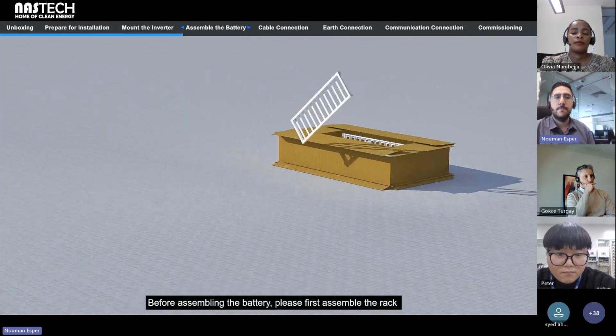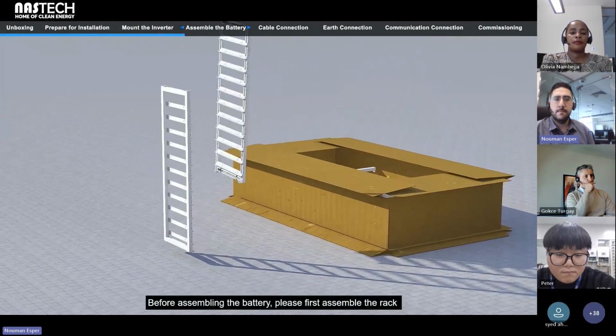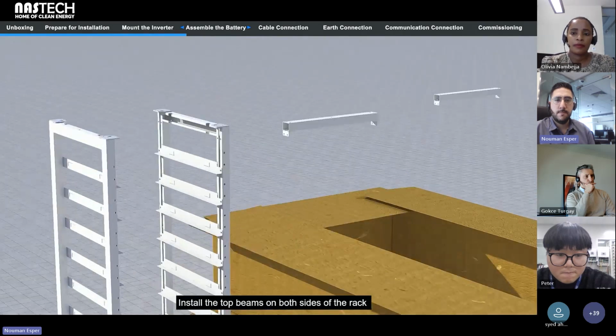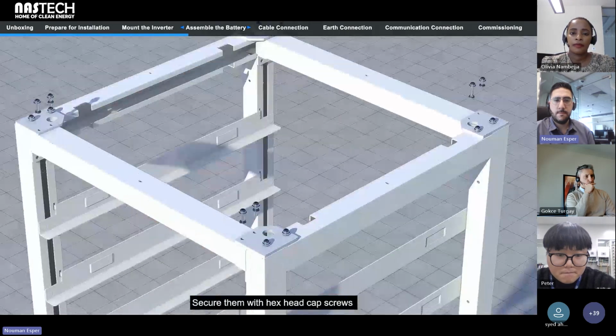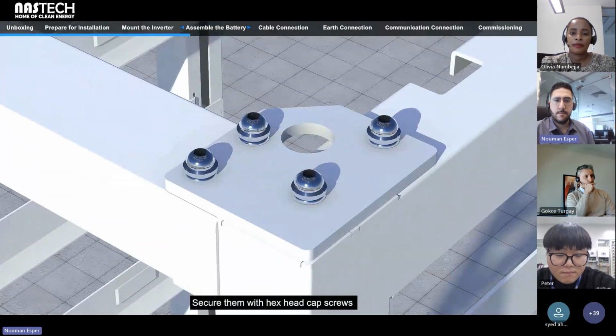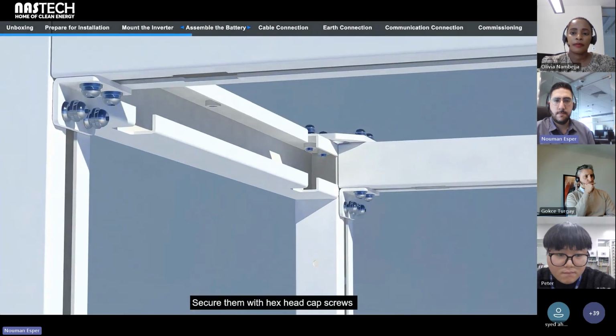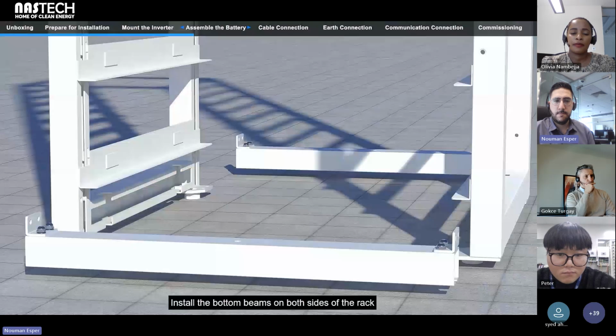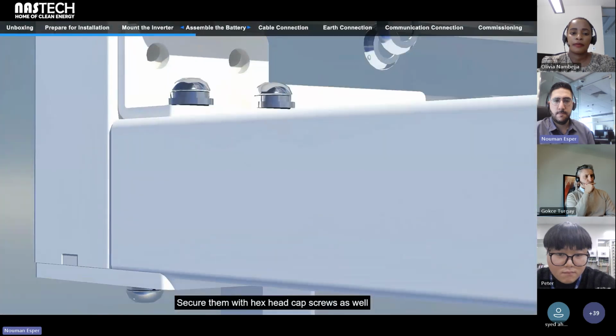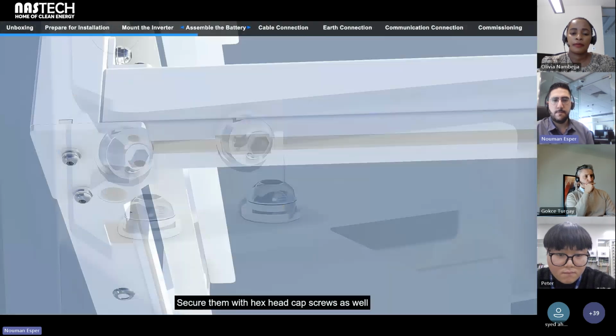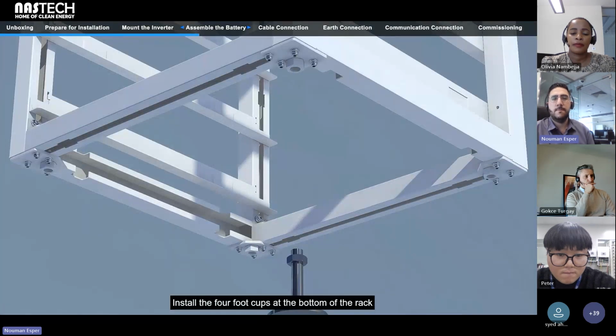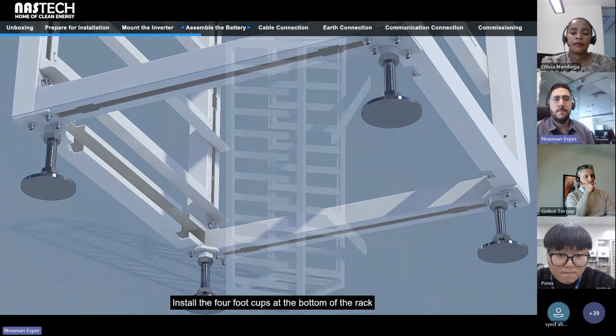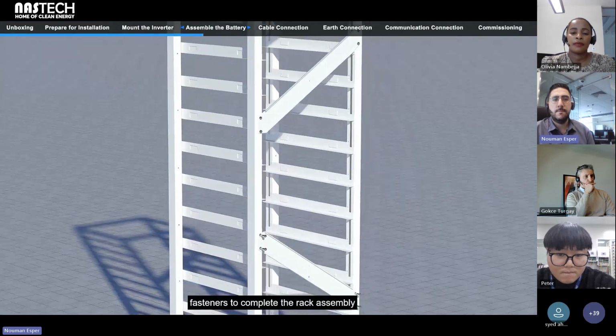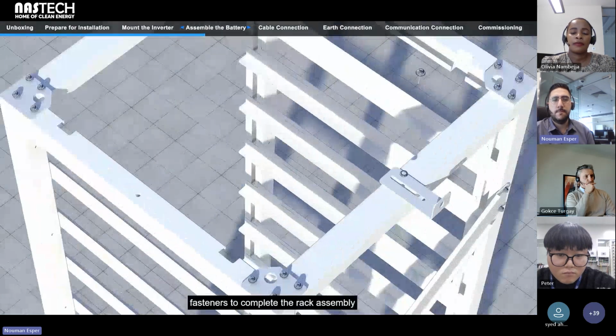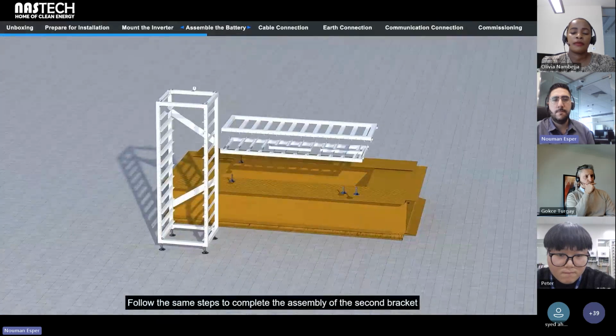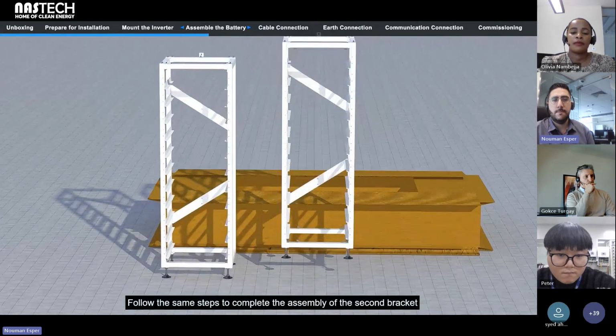Assemble the battery. Before assembling the battery, please first assemble the rack. Install the top beams on both sides of the rack. Secure them with hex head cap screws. Install the bottom beams on both sides of the rack. Secure them with hex head cap screws as well. Install the 4 foot cups at the bottom of the rack. Assemble the diagonal bracing and rack fasteners to complete the rack assembly. Follow the same steps to complete the assembly of the second bracket.